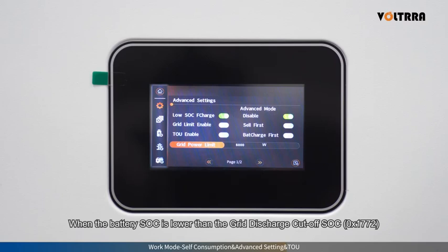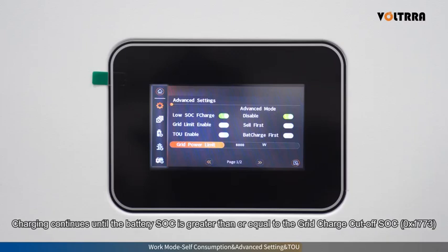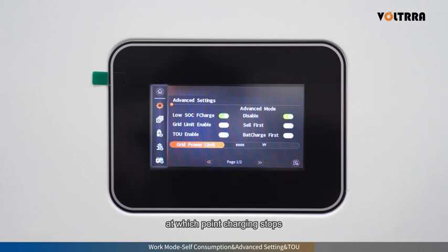When the battery SOC is lower than the grid discharge cutoff SOC, 01772, both PV and the grid will charge the battery, equivalent to battery priority mode. Charging continues until the battery SOC is greater than or equal to the grid charge cutoff SOC, 01773, at which point charging stops, and the system resumes the normal self-consumption operating logic.